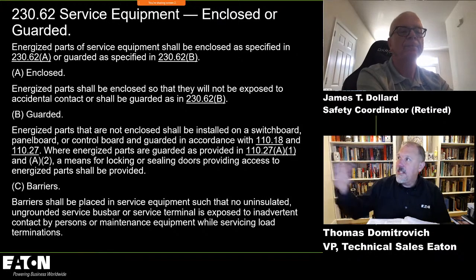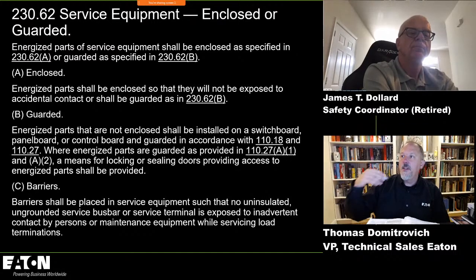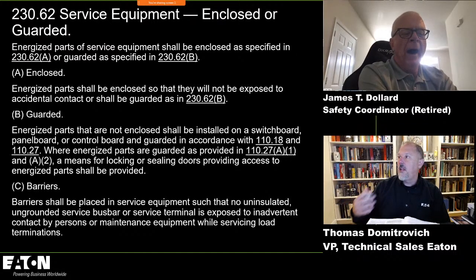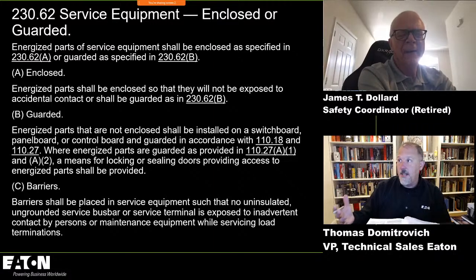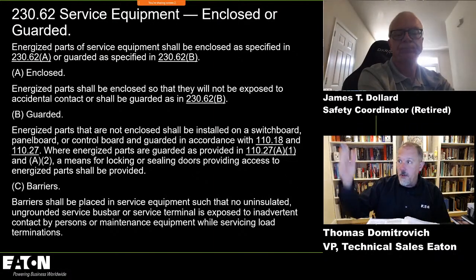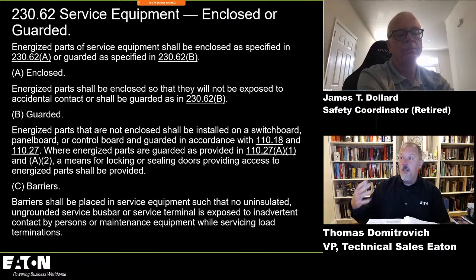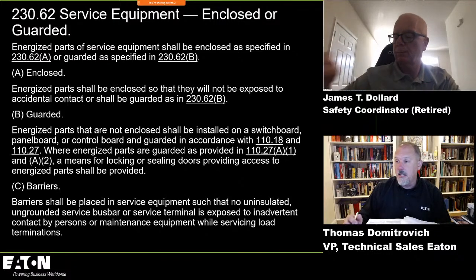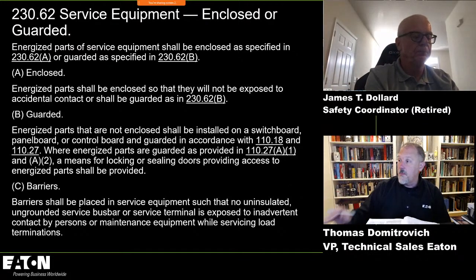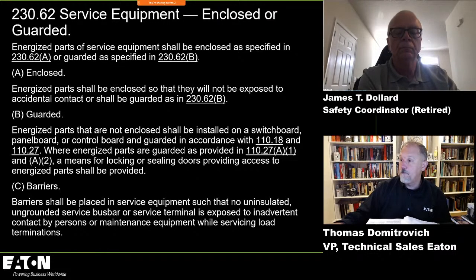So 230.62 talks about enclosed and guarded. Energized parts have to be enclosed so they are not exposed to accidental contact. Guarded: energized parts that are not enclosed shall be installed in a switchboard, panelboard, etc. And there are references to other areas in the NEC that talk about providing sealing and things of that nature. And then barriers: service equipment should have no uninsulated, ungrounded service bus bar or service terminals exposed to inadvertent contact, right?